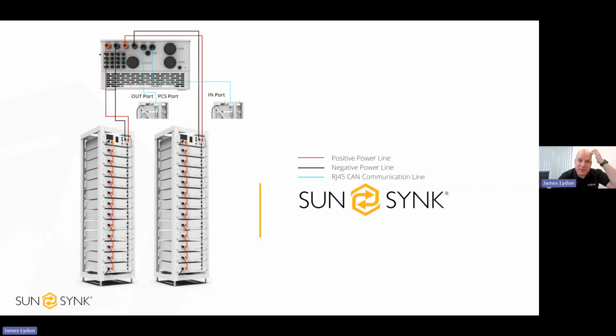This is just showing you the underside of the 50 kilowatt, showing the 2 different battery inputs. As I mentioned, there's 4 MPPTs, each with 2 strings, so you can see you've got all your MC4 connections on the bottom. And you've got your 3 main connections: your generator input, your grid input, and your load output. The load output is your UPS output, so that's whether it's the circuits or any load you want to remain powered in the event of a power cut. Your generator input and your grid.